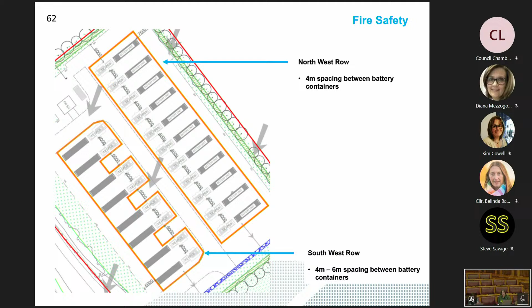As per NFCC guidance, any vegetation that naturally seeds within the lifespan of the BESS compound should be removed, and no hedgerows or trees should be planted within 10 meters of the battery containers. As demonstrated on this slide, the amended plan shows slightly less than 10 meters distance to the proposed mitigation planting to the north and northeast corner of the site, although it should be noted that the acoustic barrier is located between the planting and the battery units.